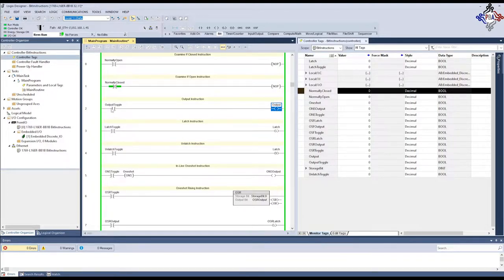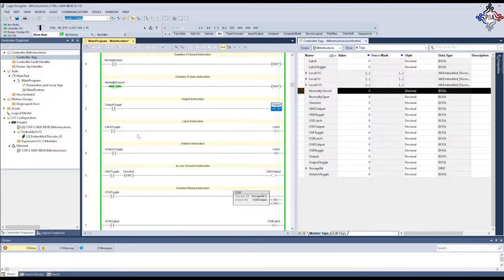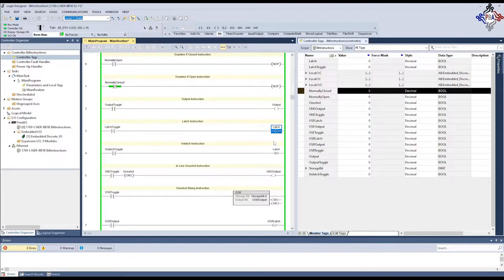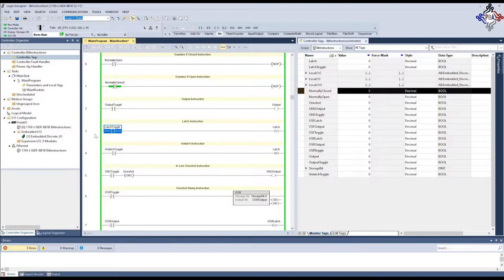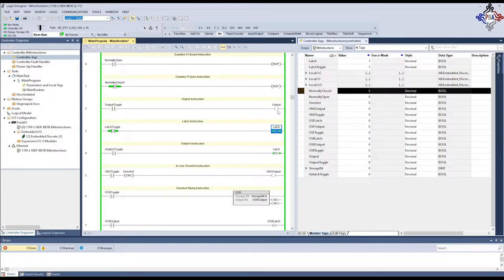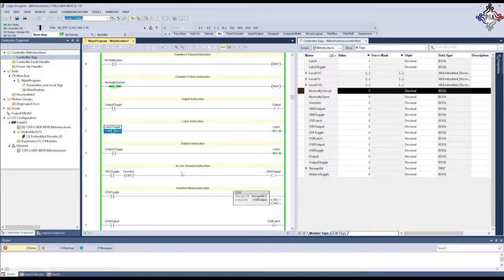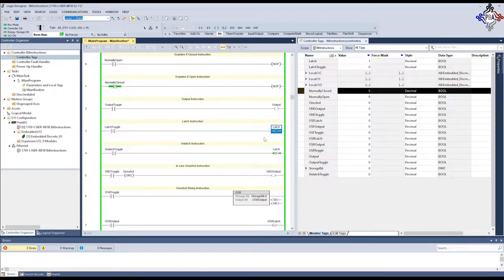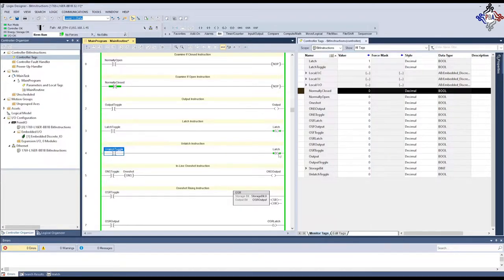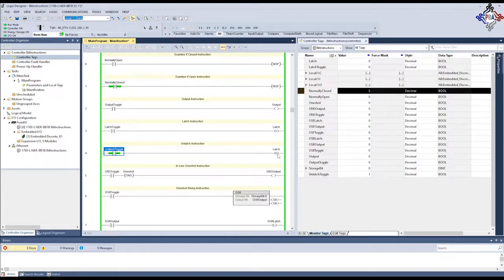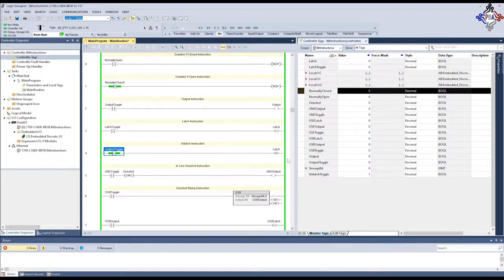Now, moving on to the latch instruction, the OTL. See up here? Output latch OTL instruction. If I turn on our latch, just like before with the output, the latch instruction lights up true. However, when I turn off the latch instruction, you'll notice it stays lit. It latches on and that output stays on until you give it the matching unlatch instruction. And that's what we have down here, the OTU, output unlatch. You have to have the tags for the latch and the unlatch stay the same. So, if I turn the latch toggle on, it latches. I turn that off and now I unlatch by hitting the unlatch instruction.